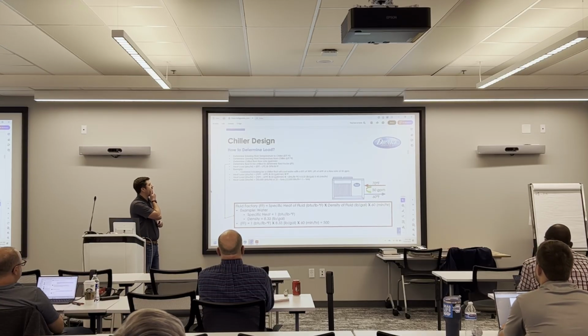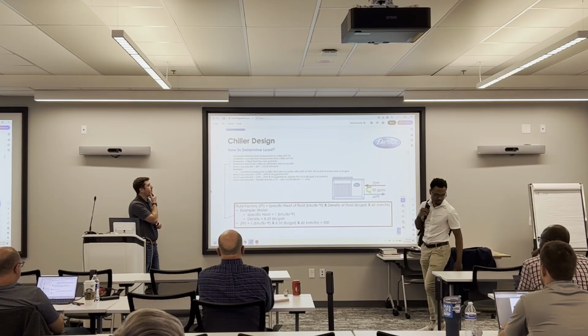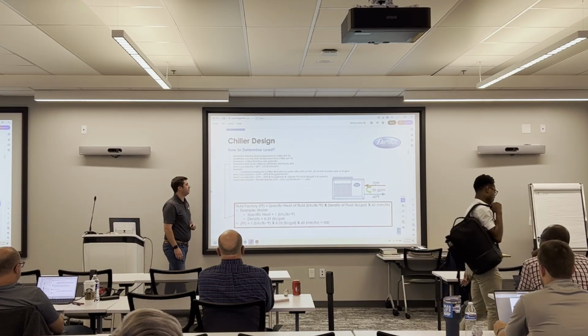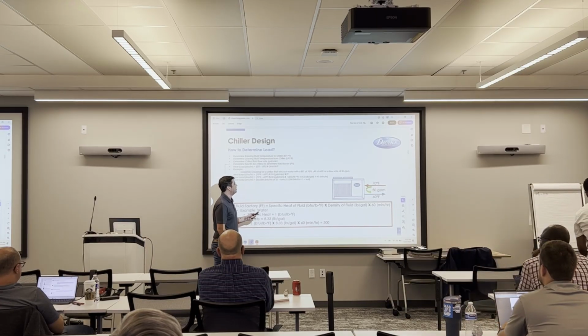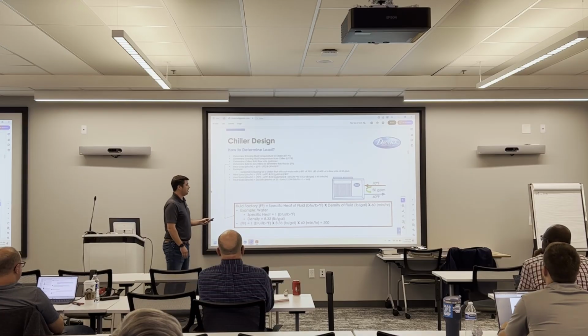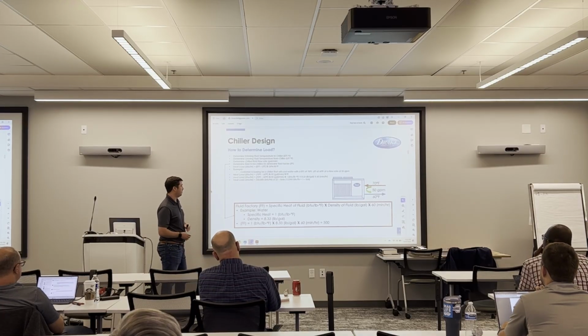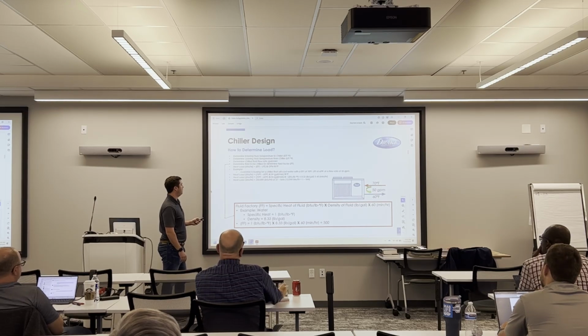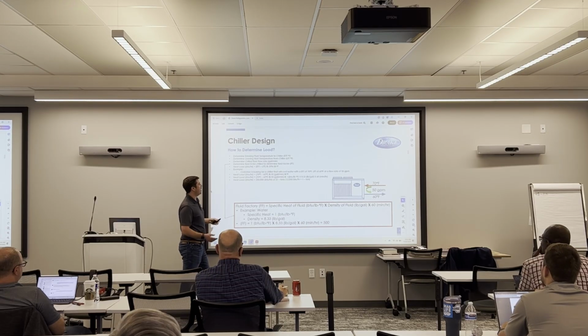All right, so I got a small example here. Let's just say a customer's looking for a chiller that will cool water. They have an entering fluid temperature coming into the chiller of 70 degrees. They want to leave the chiller at 60 degrees, and they have a flow rate of 50 GPM. That's enough information for us to quantify a load. We'll take that temperature differential, 70 minus 60, multiply that by our flow rate, and then multiply that by our fluid factor. And we're left with 250,000 BTUs per hour, or 21 tons if you're a tons guy with BTUs.